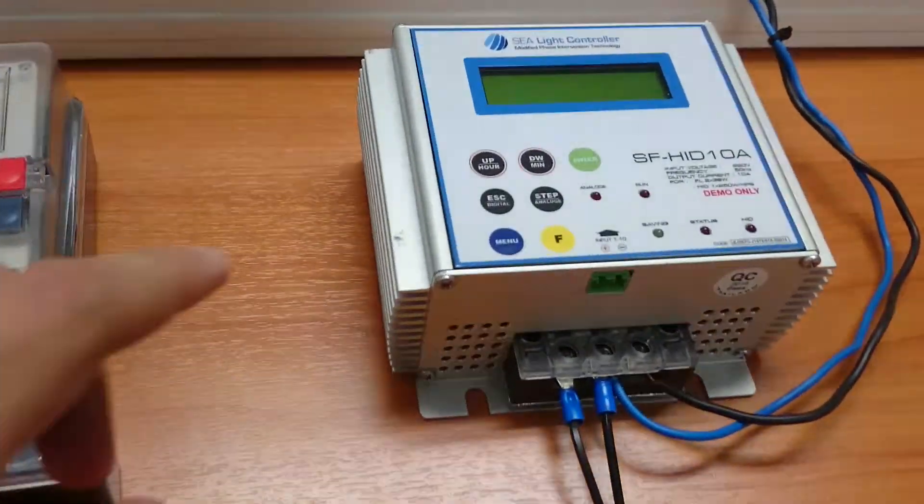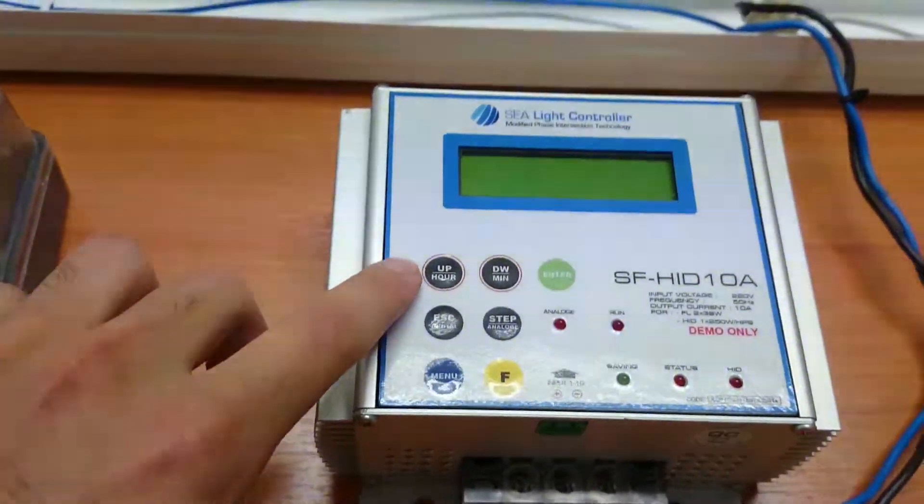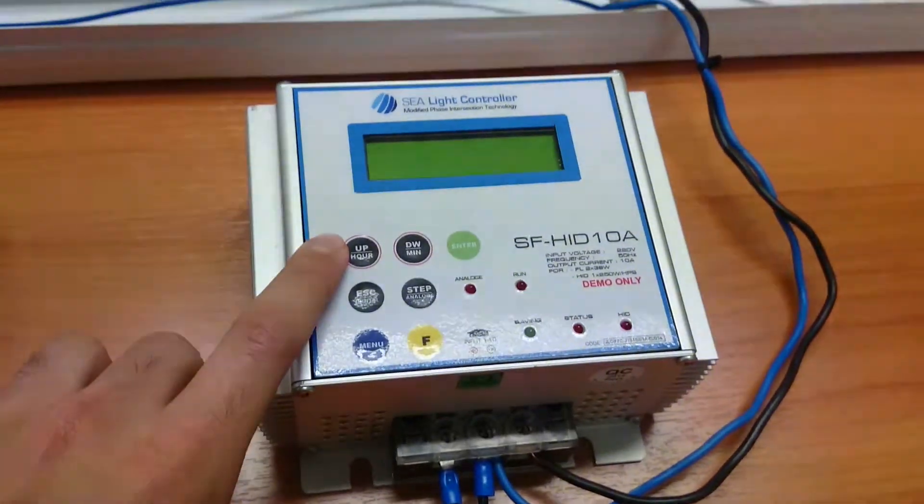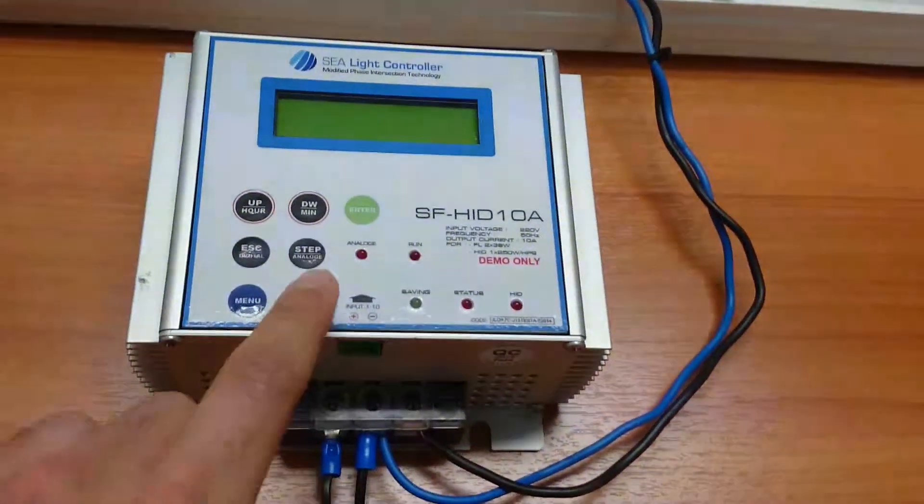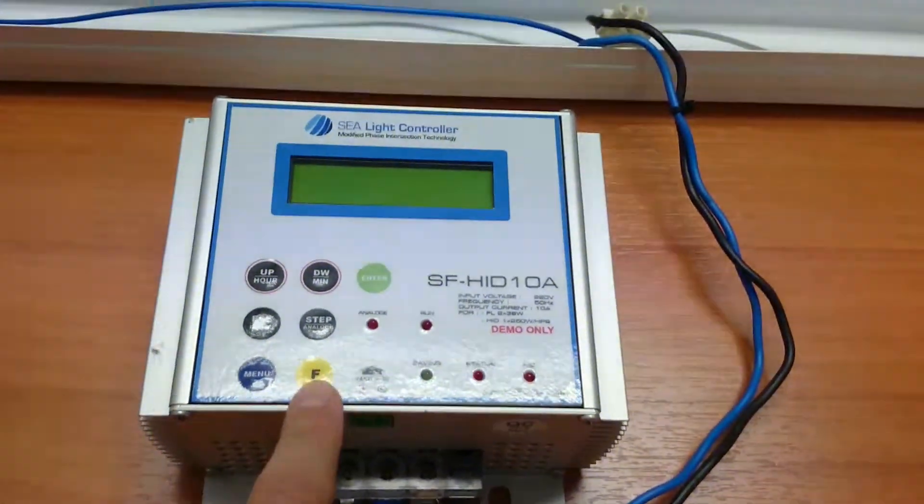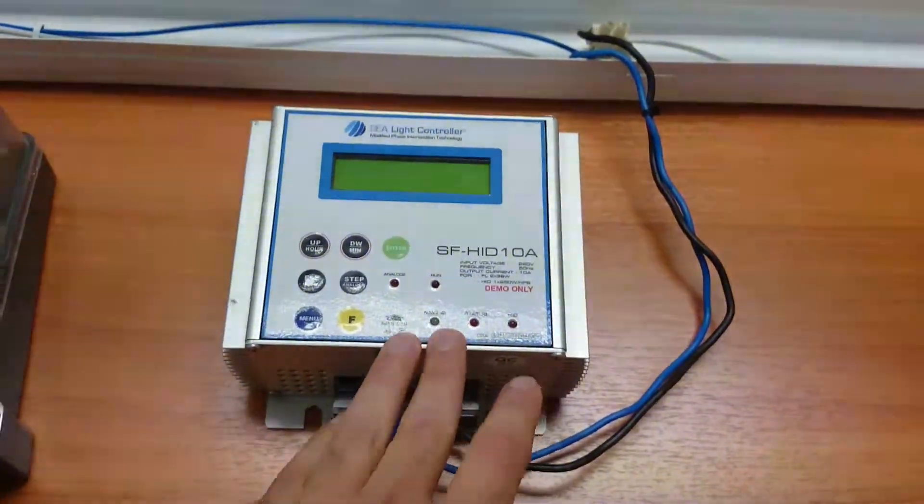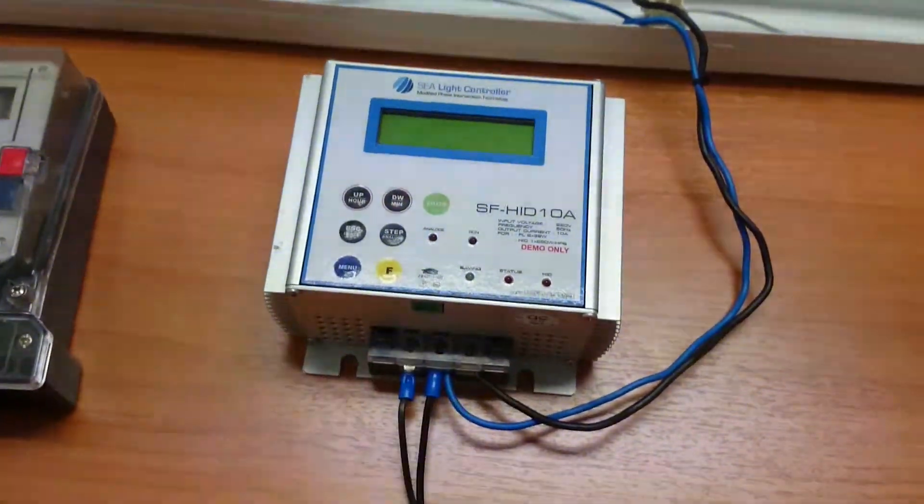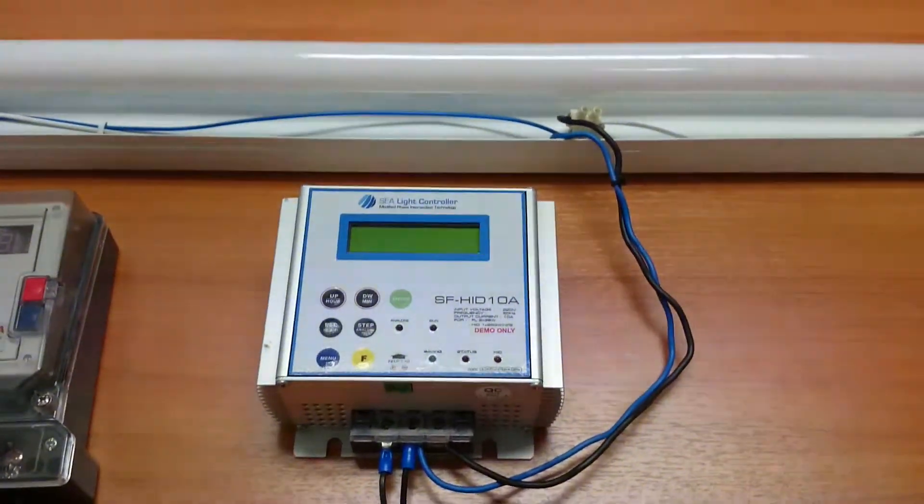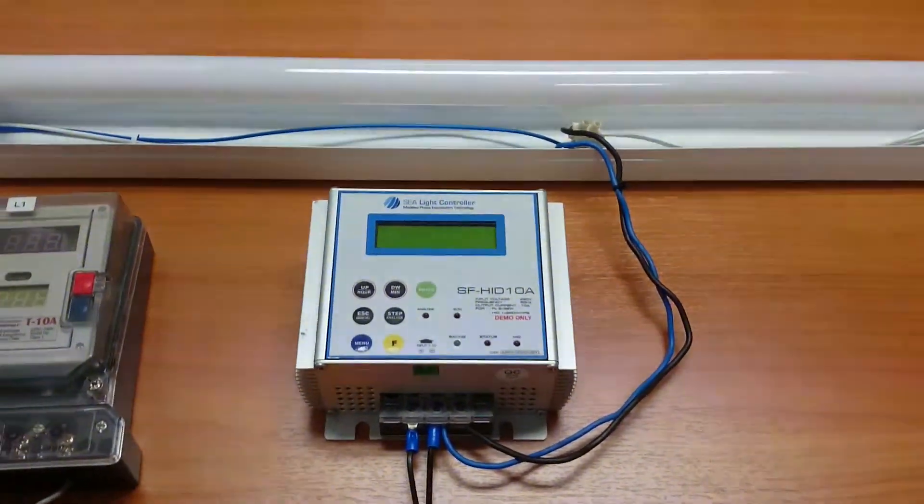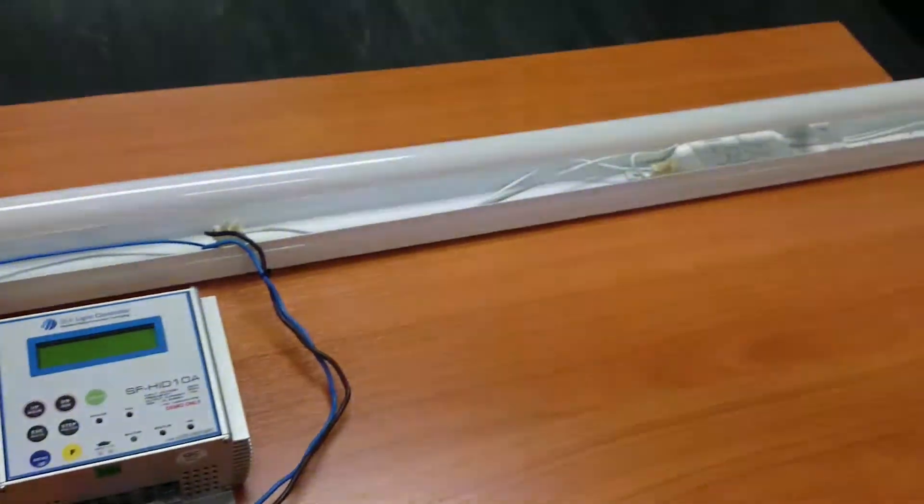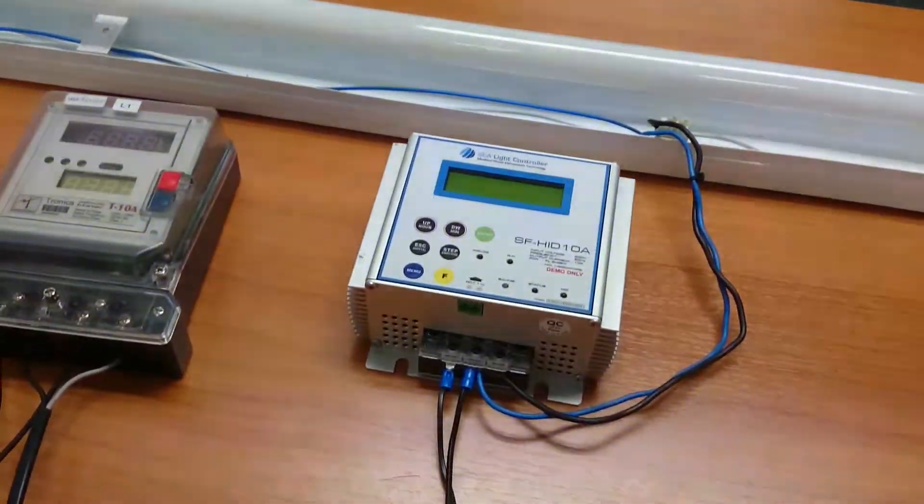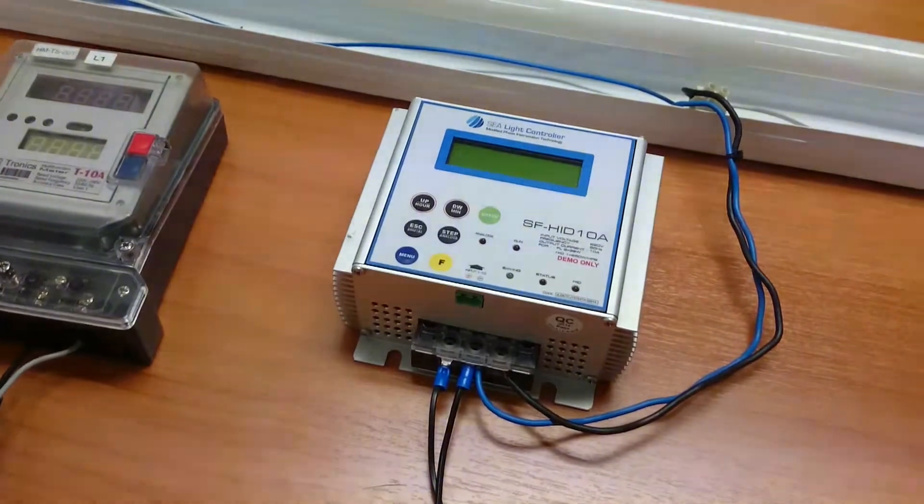Using the buttons over here in real time you can control the power consumption of your lighting. Or you can also pre-program a time schedule onto the device so that the segment controller would operate independently. So let's say at 9pm you would like the power consumption to be 80% and then at midnight you would like it to be 50%. You can program a schedule like that onto the device and it would operate on its own.